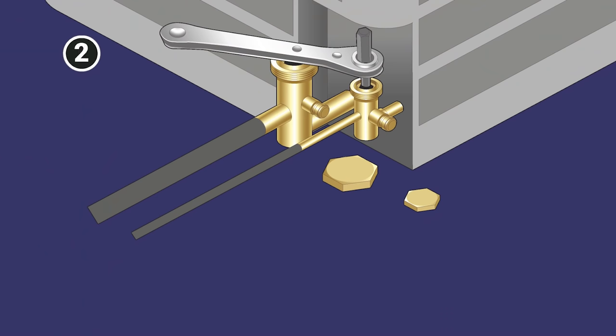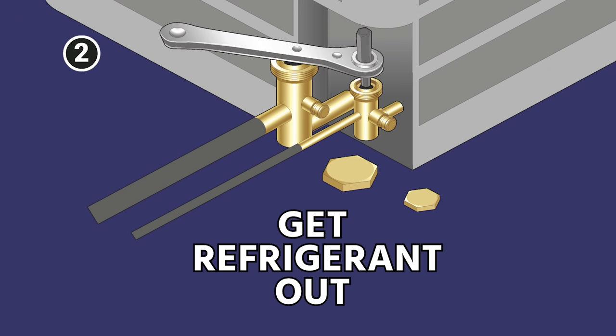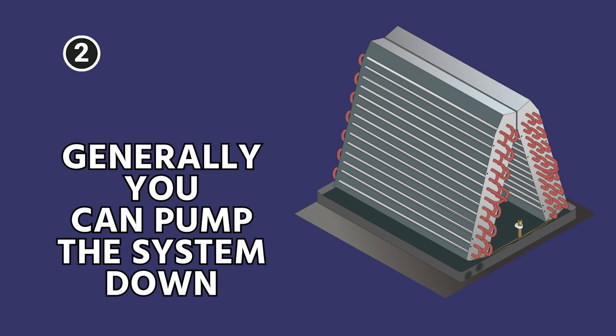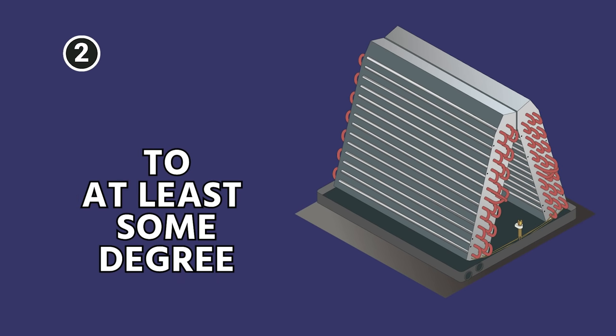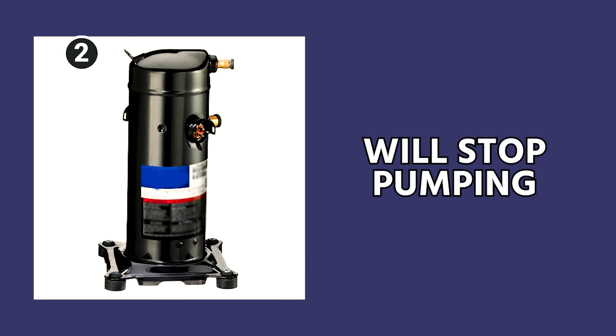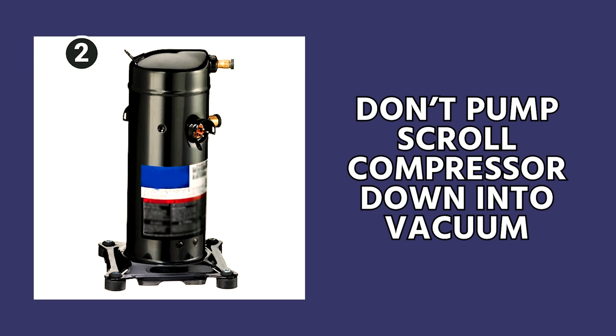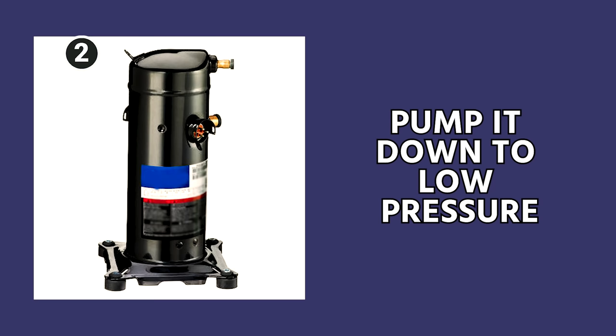Once you do that, then you want to go ahead and get the refrigerant out. Because it's an evaporator coil, generally you can pump the system down to at least some degree. In many cases nowadays, when you have scroll compressors, scroll compressors will actually stop pumping once the compression ratio gets too high, but some of them will still work okay. You never want to pump a scroll compressor down into a vacuum or really any system, but you do want to pump it down to a low pressure.